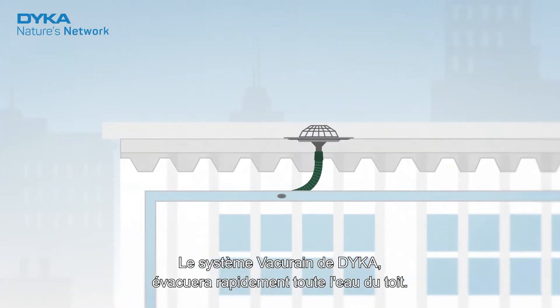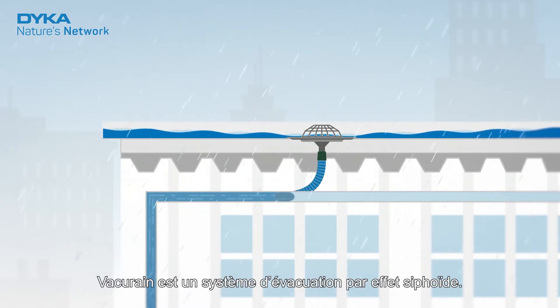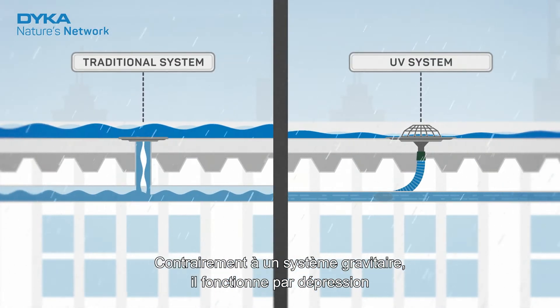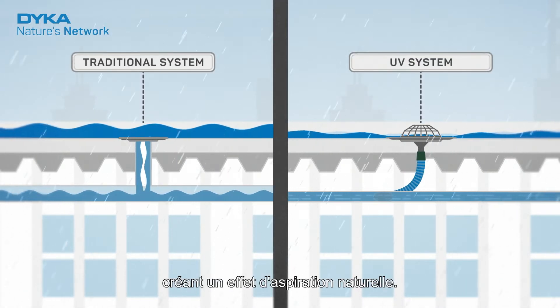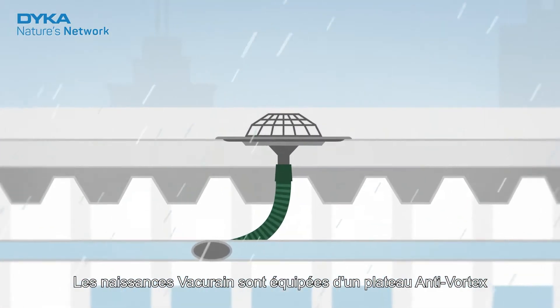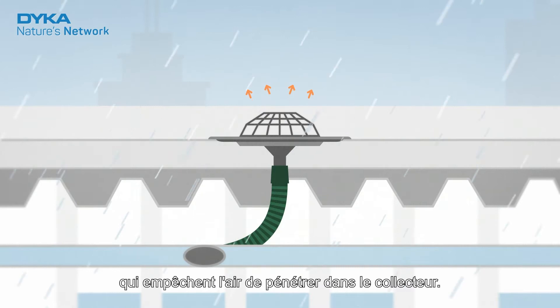DYKA's VacuRain drains the roof quickly and thoroughly. VacuRain is a so-called UV system. Unlike a traditional system, a UV system works with negative pressure. This creates a strong suction effect. Thanks to special roof outlets, VacuRain keeps air out of the pipes and water level on the roof low.